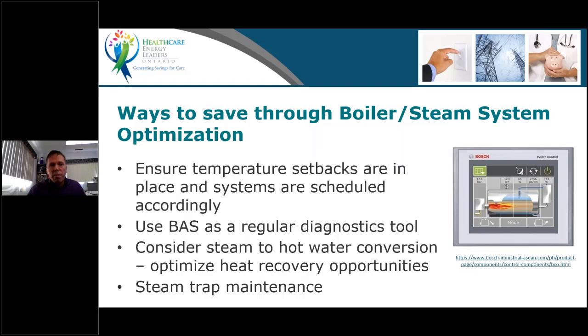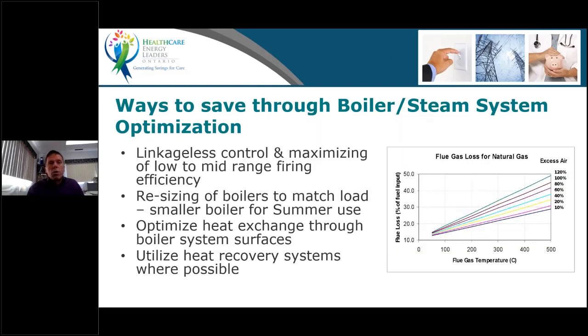Where if you have steam, obviously it is required in many hospitals. You have no choice. You have to have steam. So you can convert from steam to hot water for heating purposes, but there's other end uses where you have to remain with steam, and that means you're going to have steam traps. And steam trap maintenance is really important as soon as you're talking about steam, and also keeping the right pressure of the steam system. You try to use as low a pressure as is required at the end point where you use the steam.